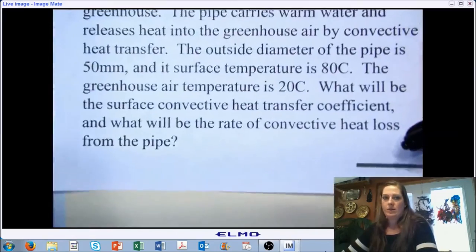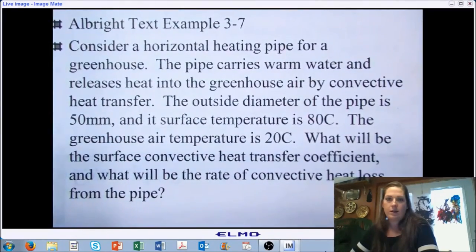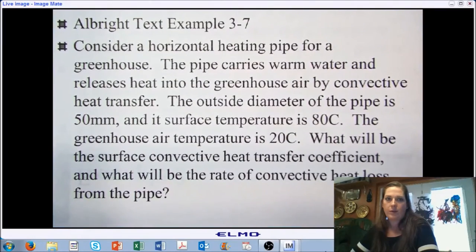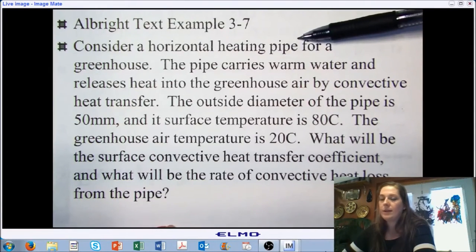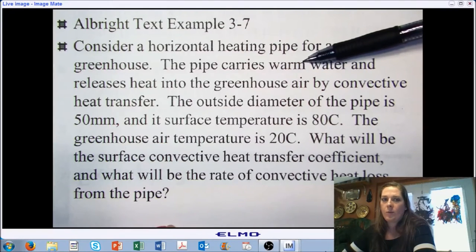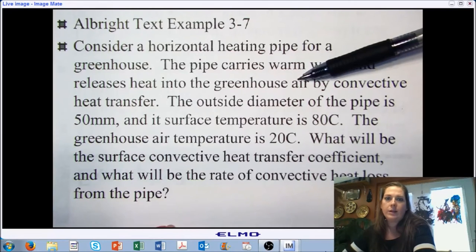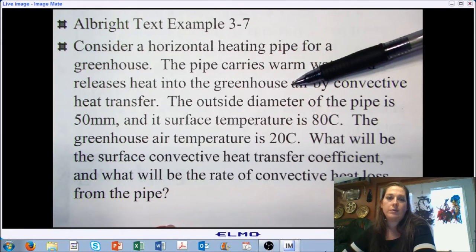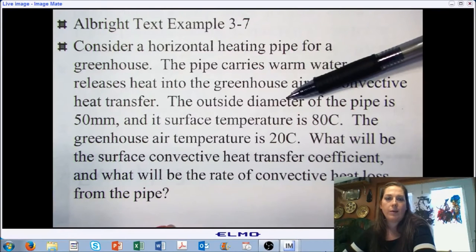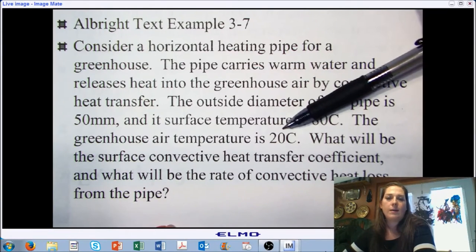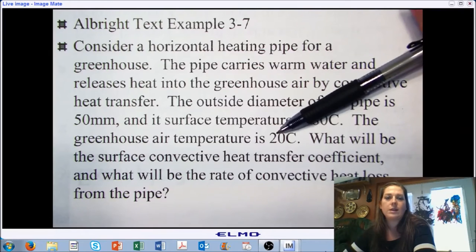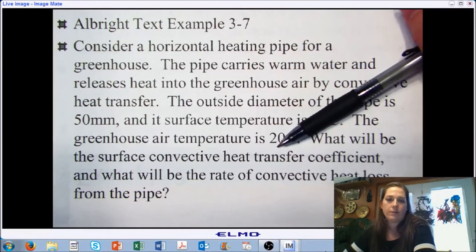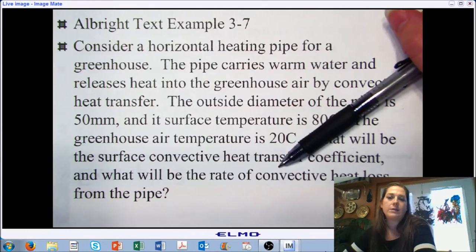So this is the example — it's worked out for you in the Albright reference material, example 3-7. We are going to look at a horizontal heating pipe inside a greenhouse. The pipe carries warm water and releases heat into the greenhouse air by convective heat transfer. We have the diameter of the pipe and its surface temperature. The set point temperature of the air inside the greenhouse is 20 degrees Celsius. We want to calculate the surface convective heat transfer coefficient and the rate of convective heat loss into the environment.